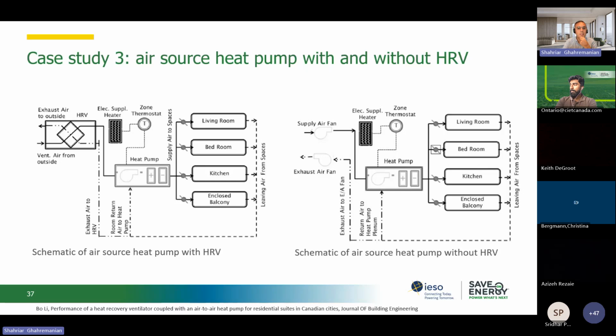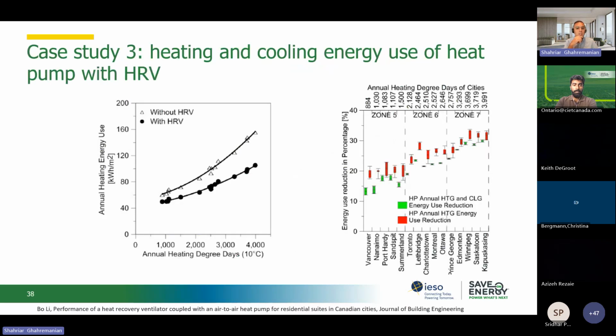The other one is the heat pump with and without heat recovery. This is a very deep, detailed study. I really loved it. If you have time, I put the link or the name of it, just search it. Take that study in a typical application where we might not need to add a heat recovery ventilator. So we say that we don't need it, and then we have a heat pump. But if we install a heat pump, this graph shows everything to us, depending on the zone. So let's say the Toronto area, it's around 3,500 heating degree days. So this is the area for Toronto.